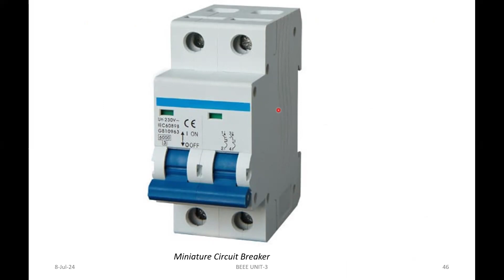Observe the working principle of MCB here. There are two types of protection: overload protection and short circuit protection. For overload protection, they use a bimetallic strip made of two metals: one is copper and the other is steel, combined together.